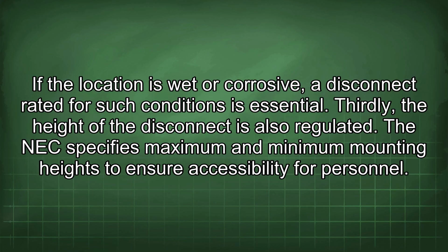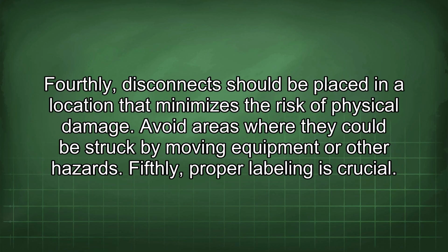Thirdly, the height of the disconnect is also regulated. The NEC specifies maximum and minimum mounting heights to ensure accessibility for personnel. Fourthly, disconnects should be placed in a location that minimizes the risk of physical damage. Avoid areas where they could be struck by moving equipment or other hazards.